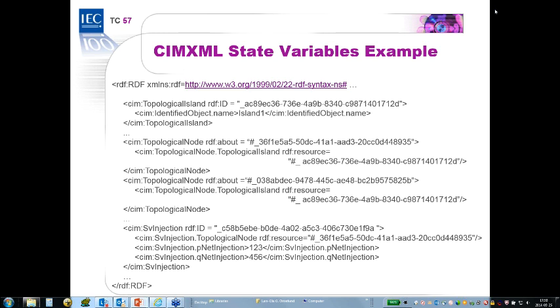basic CIM model. I haven't shown in my presentation today how this works, but there is actually documentation and descriptions of how to do this in the IEC specifications, and there are rules on the versioning of the profiles so that you can identify the version of the profile easily. And in the CIMXML data exchange format, the version of the profiles of the data that's included in a message is also described. So you can link back to the profile that was used to produce a particular message with CIM data. You might add the comment that the reason that the Working Group 13 profiles are synced is because they're used together. And so they need to be synced, but that's not in general true about CIM profiles.